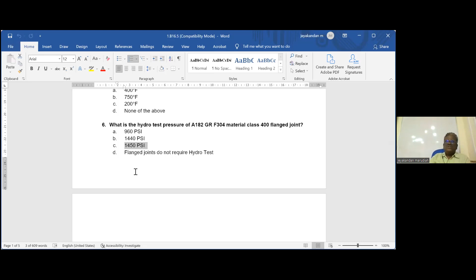This is the answer. See, what is the 100 degrees Fahrenheit rating? Multiply by 1.5. And if it does not come out round, you have to round it to the next higher 25, 50, 75, 100. Since it is coming 1440, you have to make it 1450. Suppose it comes to exactly 1450, no need to round, no need to add. So the answer is C. If it comes exactly 1450, you will not make it 1475. We will not round it. The answer should come to 25, 50, 75, 100. If it does not, you have to round it.